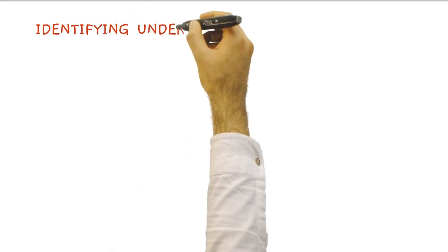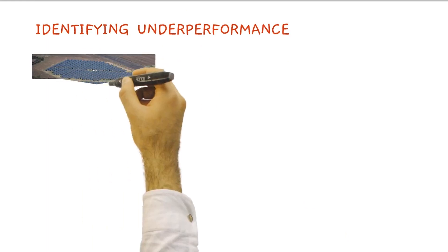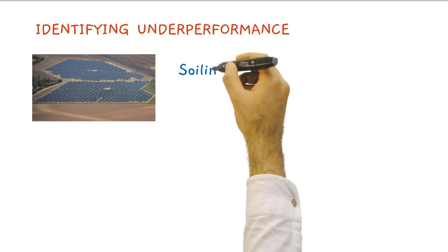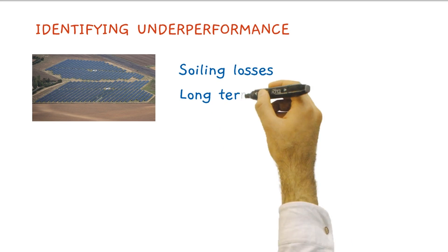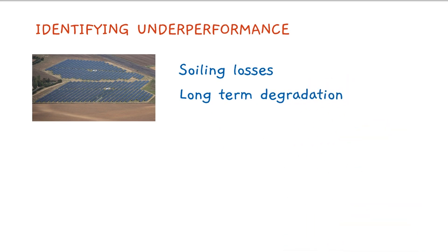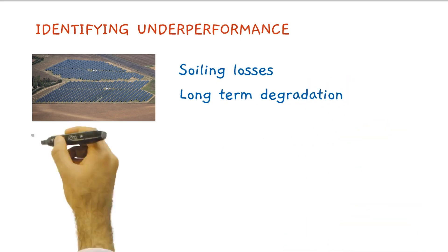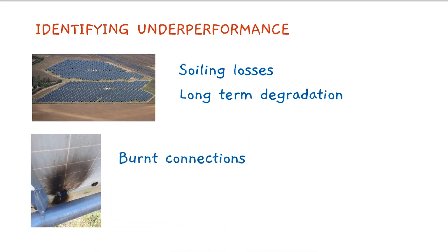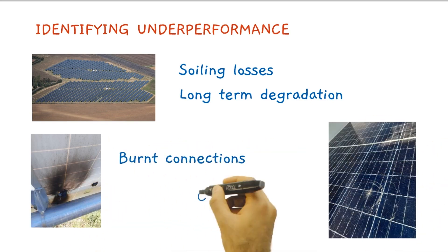IV curve tracing is an effective way of identifying underperformance of PV systems, especially in large installations like utility scale solar farms. Underperformance may be due to expected reasons like soiling losses or long-term degradation, or unexpected reasons like poor connections, cracked or broken modules, among others.